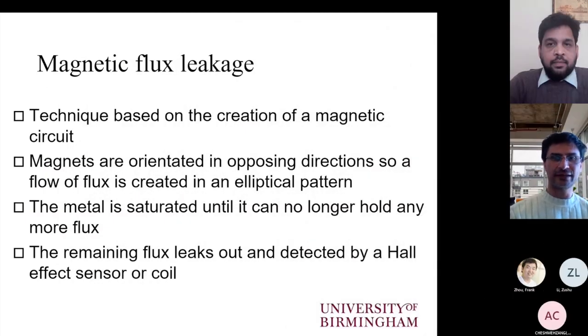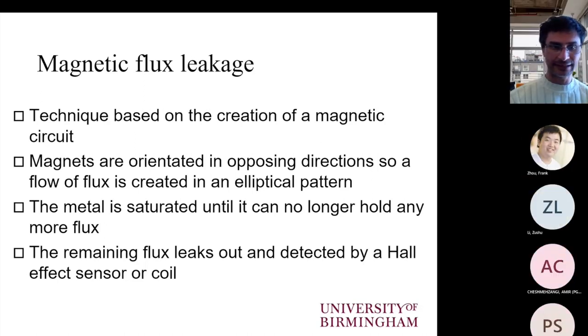So we'll start off with magnetic flux leakage, which, as I said earlier, is the earliest electromagnetic method for inspection of ferrous materials. This technique requires that we magnetize the sample, so it has to be ferrous. It cannot work with simply conductive materials, unless they are capable of being magnetized. This technique is based on the creation of a magnetic circuit, and that requires very powerful permanent magnets or DC electromagnets in order to enable this method to be applied for the inspection of ferrous materials and ferrous components.